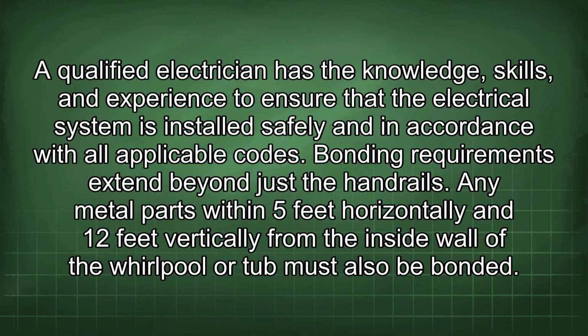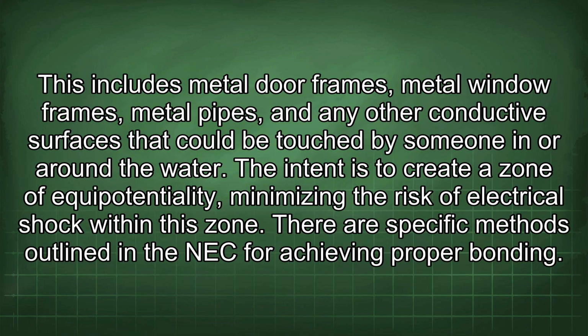Bonding requirements extend beyond just the handrails. Any metal parts within 5 feet horizontally and 12 feet vertically from the inside wall of the whirlpool or tub must also be bonded. This includes metal door frames, metal window frames, metal pipes, and any other conductive surfaces that could be touched by someone in or around the water. The intent is to create a zone of equipotentiality, minimizing the risk of electrical shock within this zone.